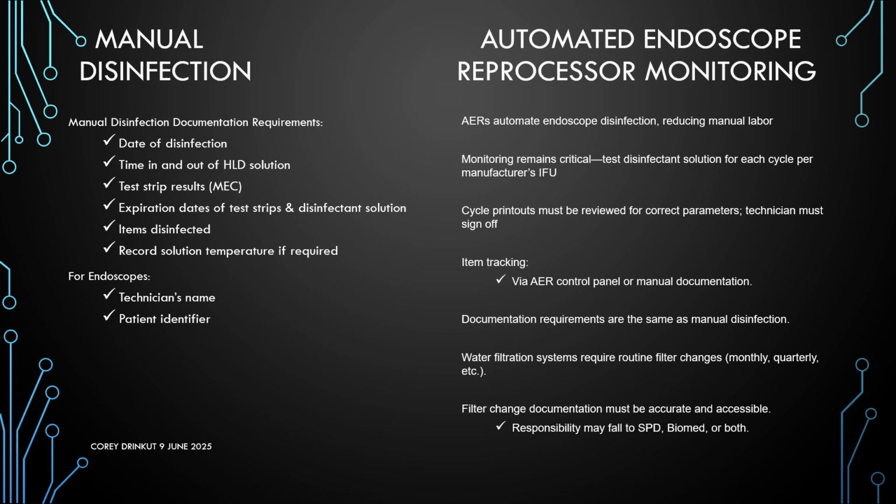The AERs, or the automated endoscope reprocessor, streamline the disinfection process, but diligent monitoring is still essential. With the AERs, there is a printout, just like your steam and your V-PRO sterilizers. It prints out. With the AERs, it does the same thing. It prints out all the information.